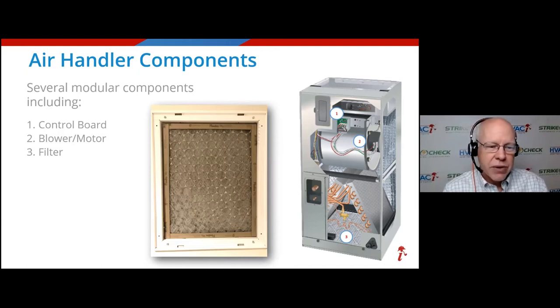All right, so I said we needed filtered air. So the question is why do we need filtered air? A lot of people think we put filters in there because I have ductwork and I don't want all that dust, dirt, debris, mold spores coming out of my ducts and landing on my head and getting my dining room table dirty and things like that. Well, that's not why we have a filter. Has nothing to do with humans. All right, we don't put filters in HVAC systems traditionally for humans.